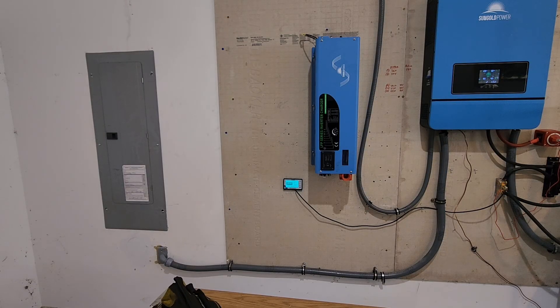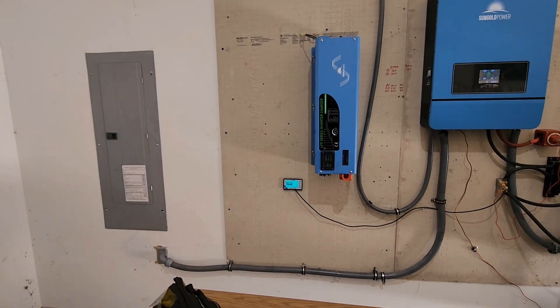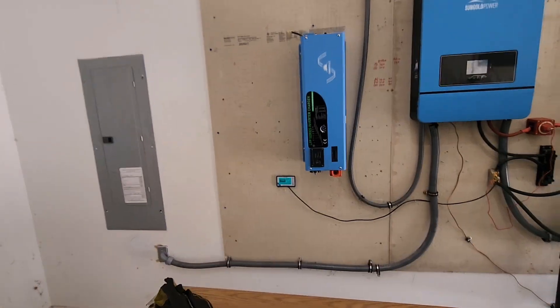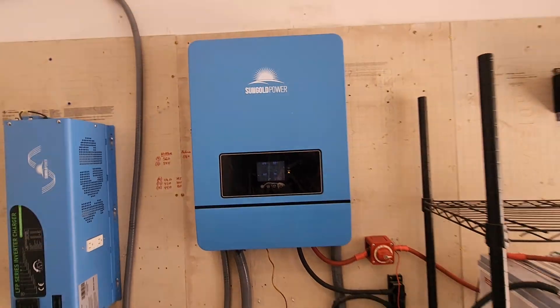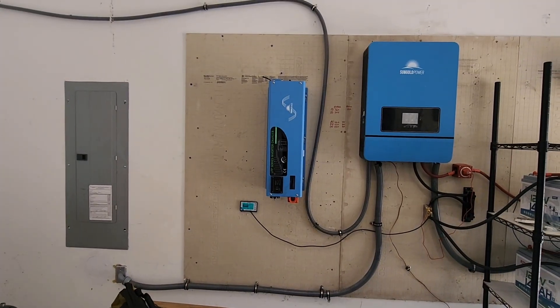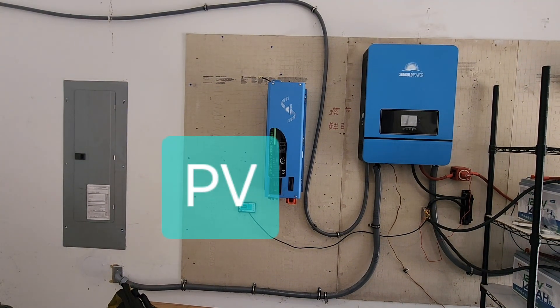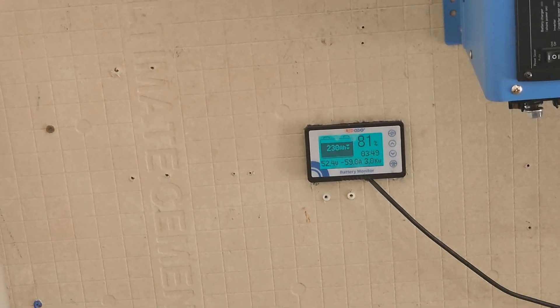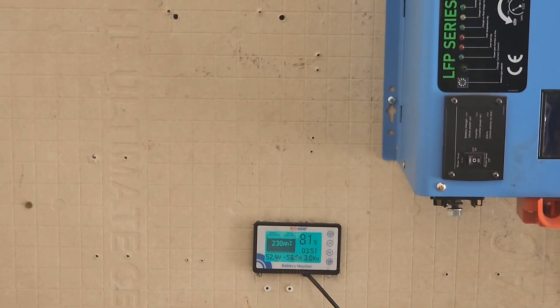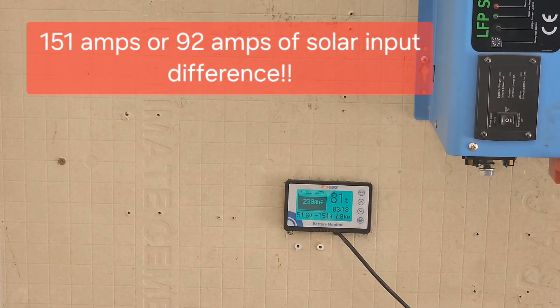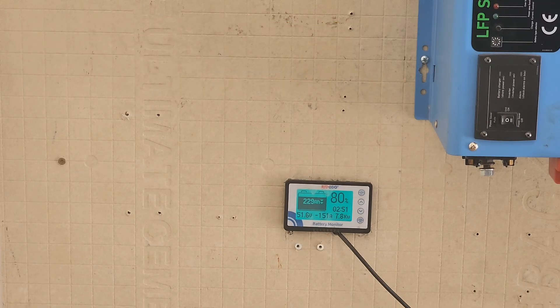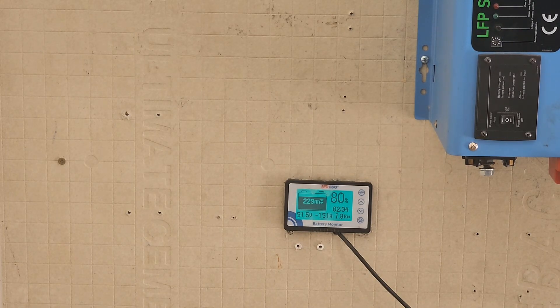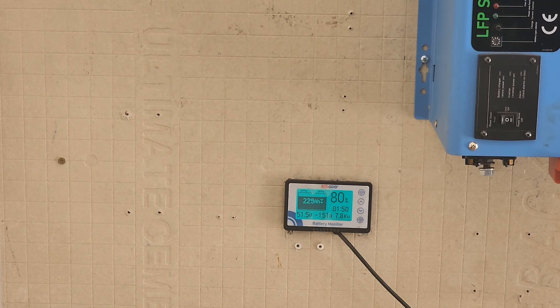So what I'm going to do now is shut off my solar. That way you can see what the power is going through the actual shunt. The shunt is the difference between what's coming in and what's coming out. As you can see, I am at 4 kilowatts each leg going out. Now I'm going to shut off the AC. But again, since the shunt shows the difference, that's only going to show 3 kilowatts. You're going to see what happens when I turn off the solar, how much that goes up. That number should be a lot higher now. 150 amps. And again, nothing changed on the input. Still 4 kilowatts each leg or so.